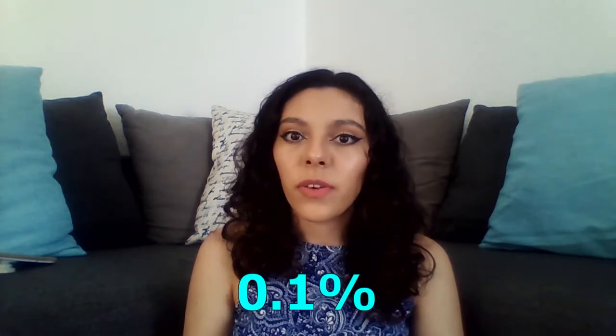Now, the final diameter ratio of the selected primary element is determined by successive approximations according to the approximation desired in the calculation, which is usually 0.1%.